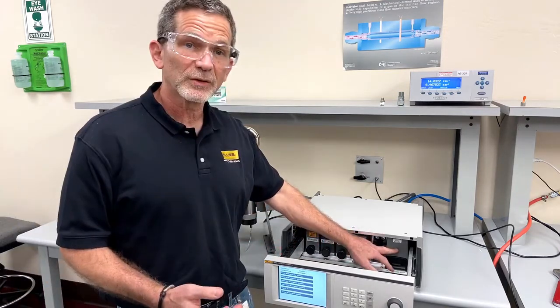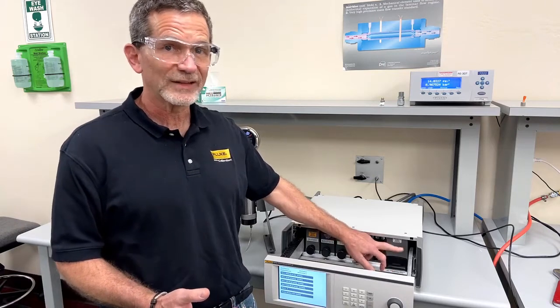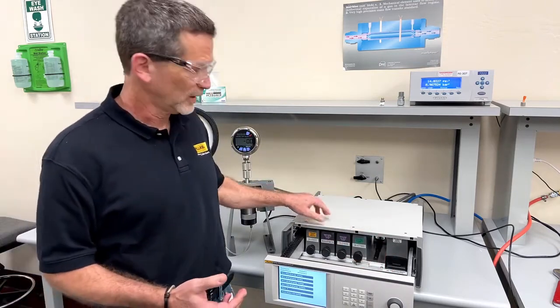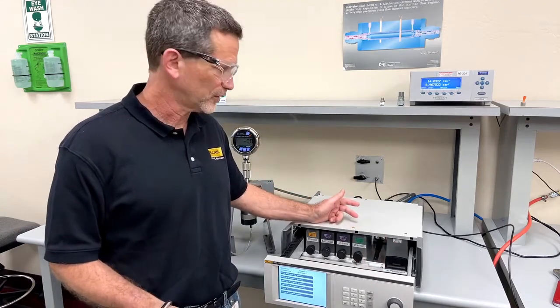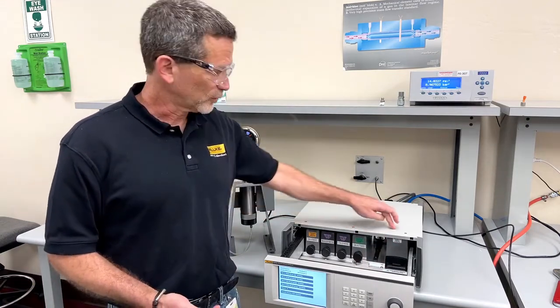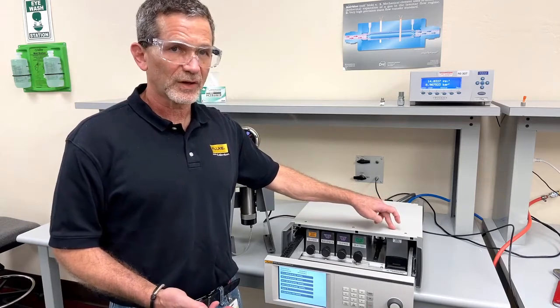The last module over here is the pressure control module. That's really the main difference between the three chassis. The pressure control module is what allows the controller to set the pressure. This is what happens to be a 6,000 PSI module.